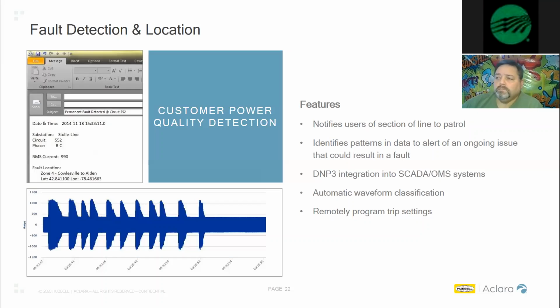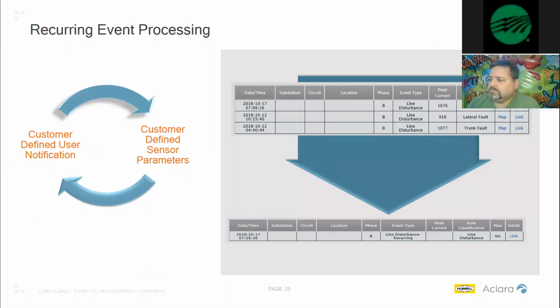Okay, the second method we use, which is an important one as well, is our circuit distance to fault estimation. Anytime the sensors on the feeder detect a fault condition, we record an RMS fault magnitude. If the utility has the ability to do this, which most seem to have, you take that RMS fault current value and plug it into a circuit impedance type model. Using the fault current value in conjunction with that impedance model, it can give you a representation of different areas where that fault could have occurred. You can then use that to tell dispatch or linemen where they might want to look based on where that fault current should be on that feeder. That's a big advantage with the sensors. We've done a lot of testing so that our fault current values are very close to what Schweitzer, who's the leader in those relays and their measurements, gets, so they fit into all these impedance models.